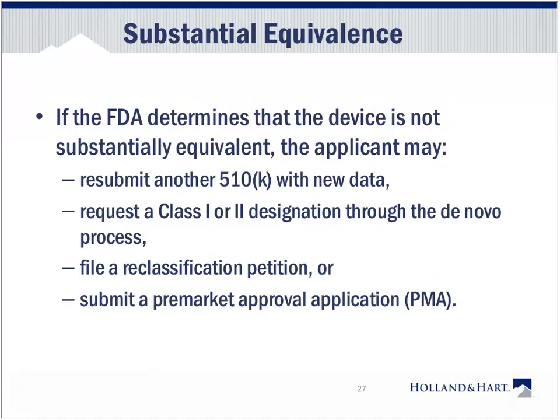What happens if the FDA determines the device is not substantially equivalent? Well, in that case, the applicant can resubmit another 510K with new data, basically making a better case that it is substantially equivalent. They can request a Class 1 or Class 2 designation through the de novo process, and I'm going to give you a site for the de novo process, but that's beyond what we're capable of covering today. They can file a reclassification petition, or they can submit a pre-market approval application, that being the most onerous, expensive, and time-consuming pre-market approval process for Class 3 devices.